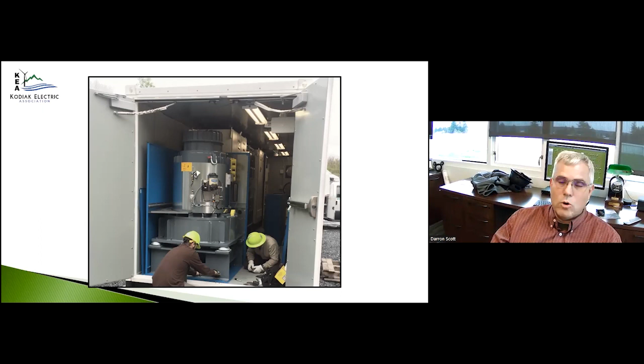So that's kind of how our system works in general here. We've got to keep 60 cycles, just like everybody else in the US does. From that, you've got your loads going out, whether it's seafood processors, Coast Guard, or whatever, and then you've got power coming in from Terror Lake. Terror Lake is our cornerstone, good base load power - base load meaning we can ask for something and it's going to give it to us. It's controllable. The wind turbine just gives us what the wind turbine gives us - we can do some control on it, but we don't do that very often.